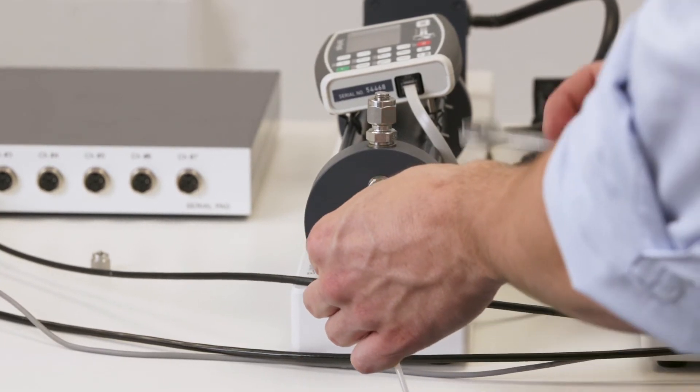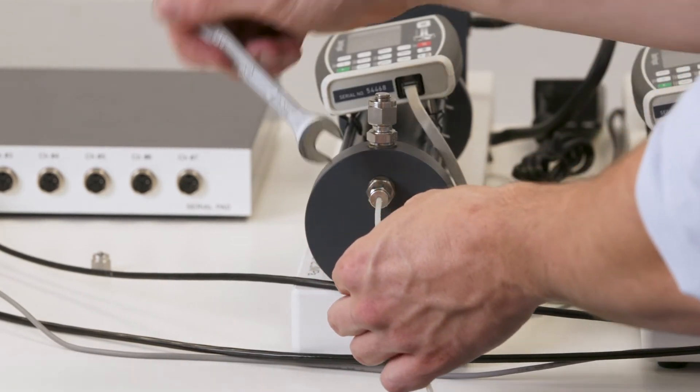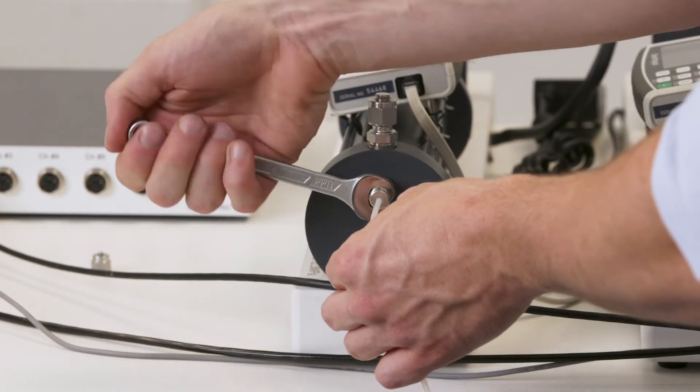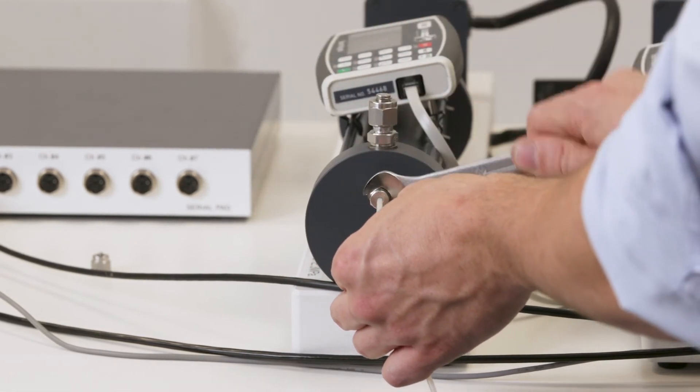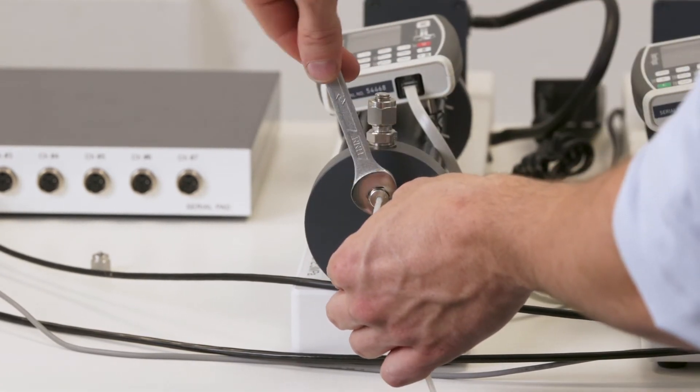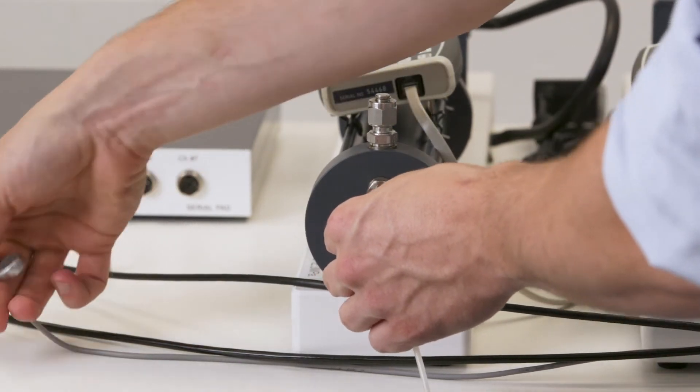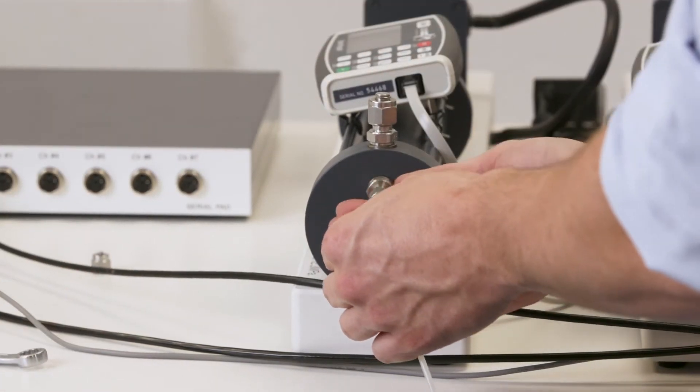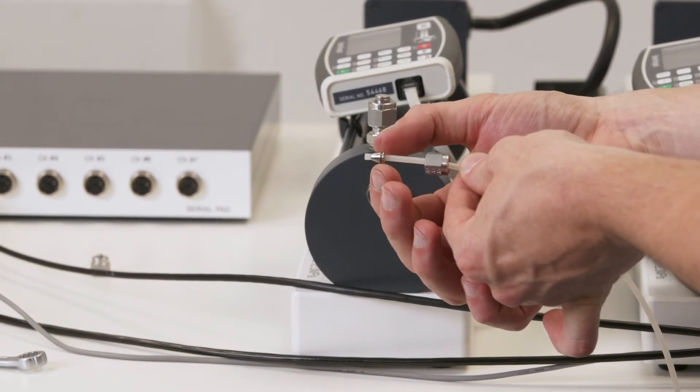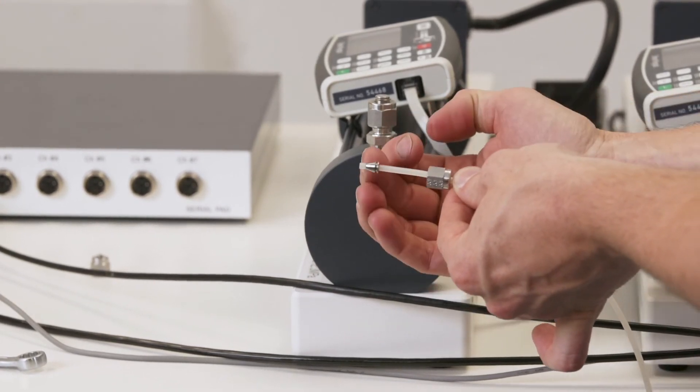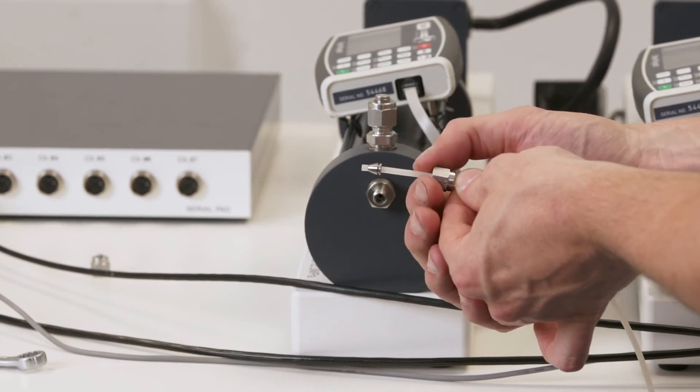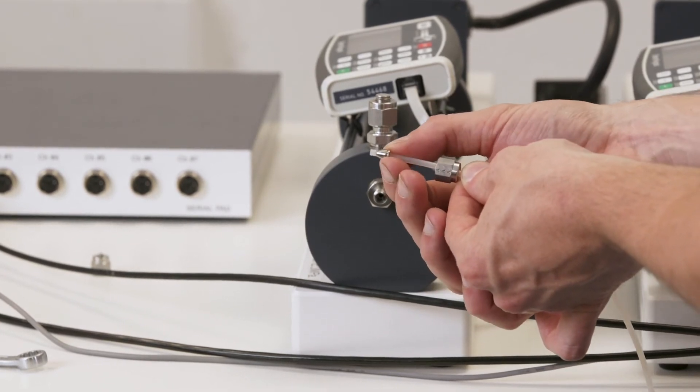At this point, this is a first initial connection, so we're going to want three quarters of a turn. We'll go a half and then an additional quarter. We'll just back that off and we can unwind it by hand. What we'll see now is these are fitted and securely connected at the front with a nice little bit of tube just sticking slightly out the front of the cone there.